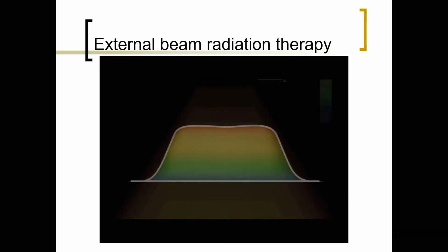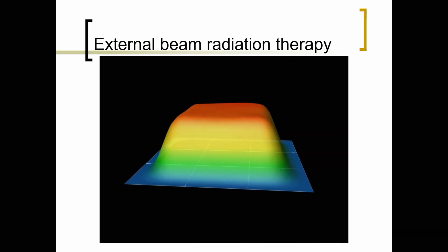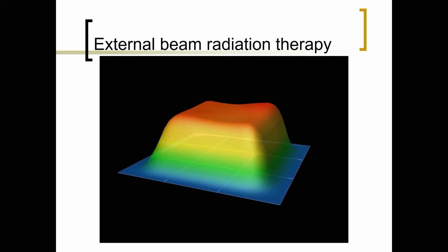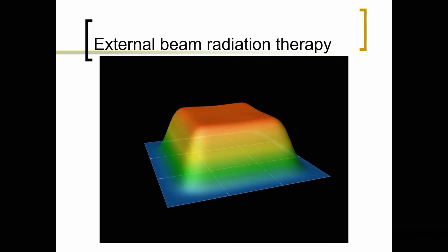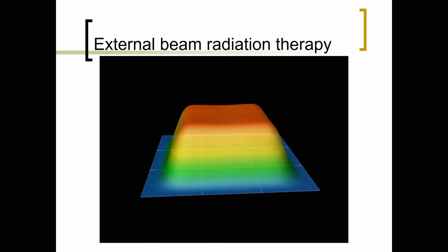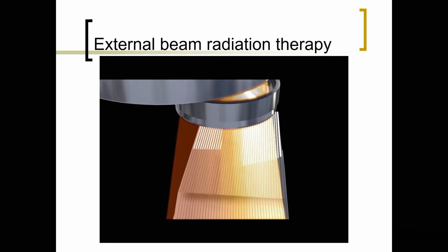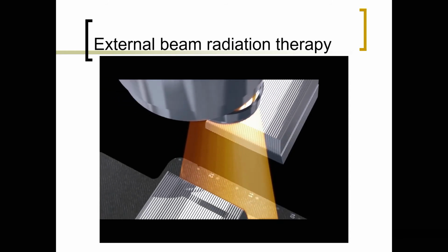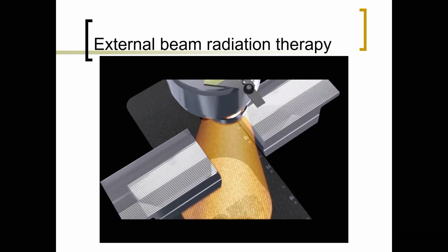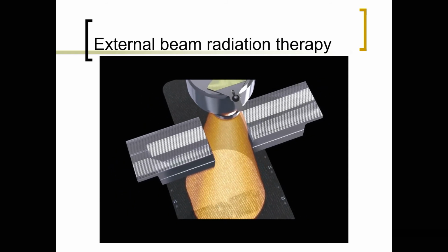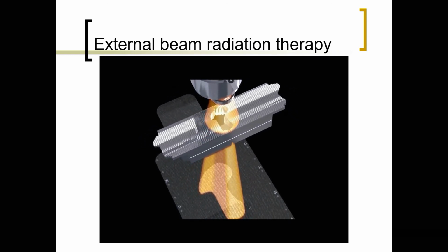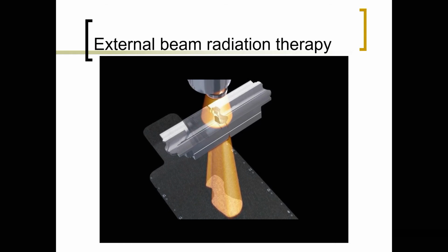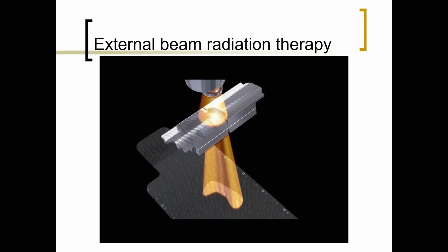The treatment machine must replicate the beams modeled within the planning system. This is critical to the accuracy of treatment delivery. A beam quality function is performed by a third ionization chamber, which uses 7 electrodes to monitor different sections of the radiation field. The X-ray beam is almost ready to treat the patient. Before that, further beam shaping is required to ensure that the shape of the delivered X-ray beam matches the shape of the tumor. This is done using a multi-leaf collimator, a number of fine tungsten leaves which move independently of one another and can create a variety of complex treatment shapes.